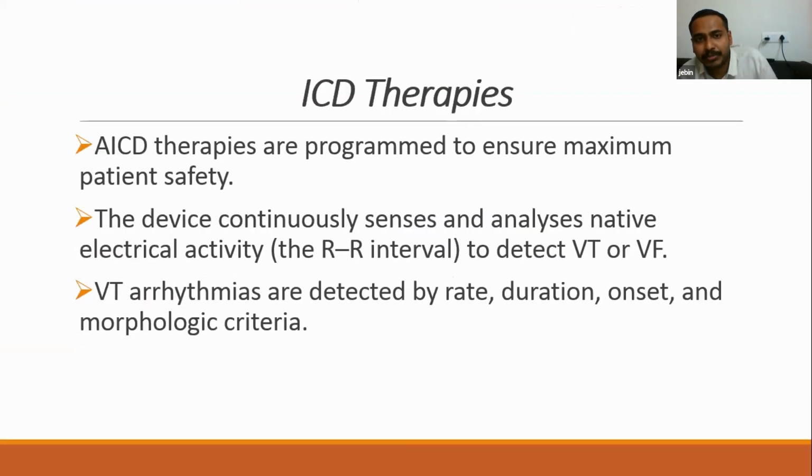The therapy is provided by the ICD. The ICD therapies are programmed to ensure maximum patient safety. The device continuously senses and analyzes native electrical activity to detect any VT or VF. If VT arrhythmias are detected, they are detected by rate, duration, onset, and morphological criteria.